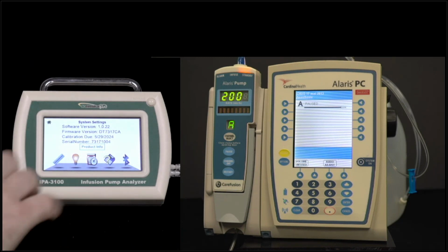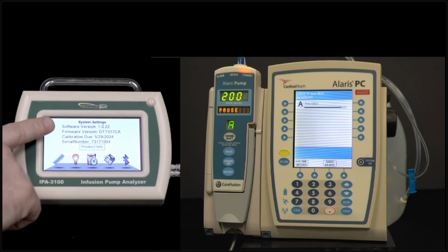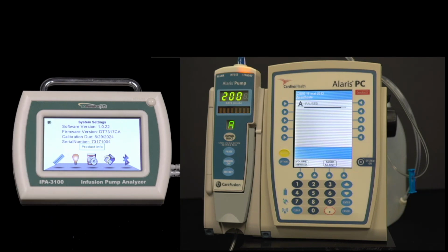We are compatible with Apple and Android devices. The other interesting information here: we have the software version and firmware directly on the screen, as well as when the calibration is due. As they get closer to that calibration due date, a message will pop up saying your calibration is due soon, so you can schedule it and don't have to worry about being out of calibration or in a panic to get the unit in for cal.